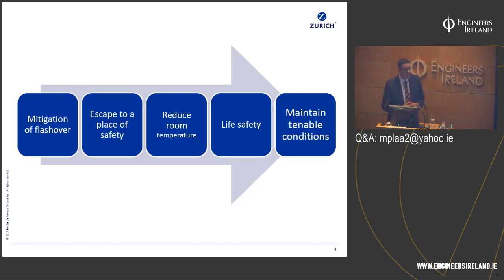So it's our opinion within Zurich that because most of these systems, and I'm really focusing now on the land-based market, because this is where water mist is moving into the traditional domain of sprinklers, the marine market of machinery spaces, combustion turbines, etc. is well established and has a proven history for water mist. However, because the systems are predominantly partial in nature, it's important to be clear that these systems are predominantly installed for life safety purposes. And they're there for these reasons here.